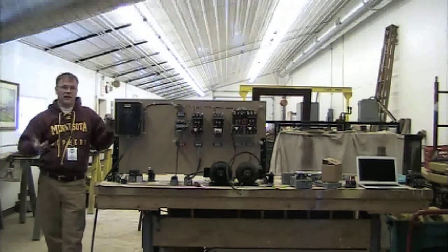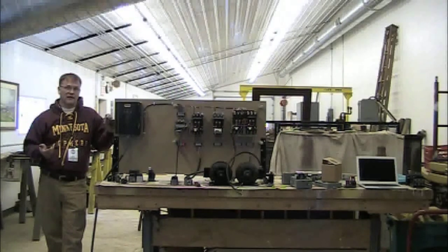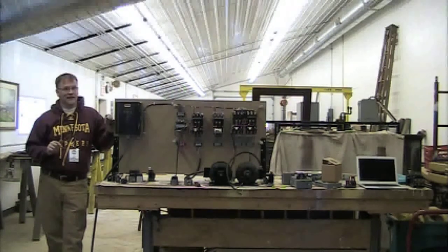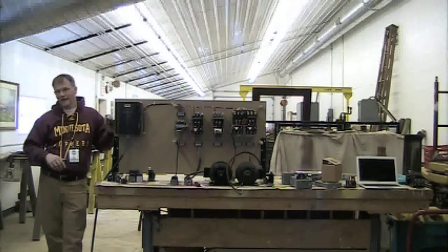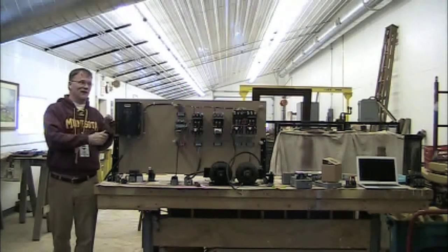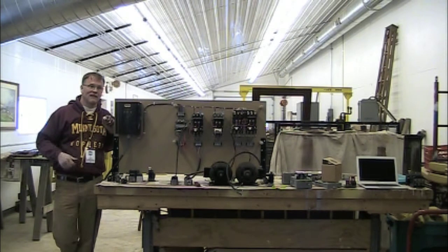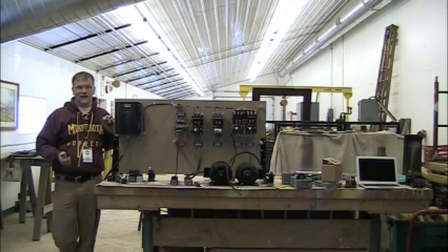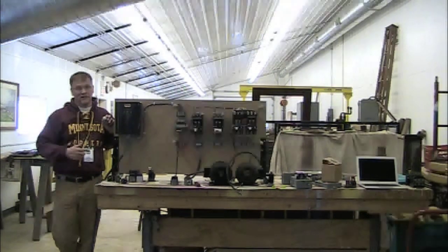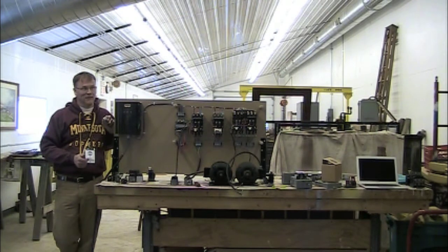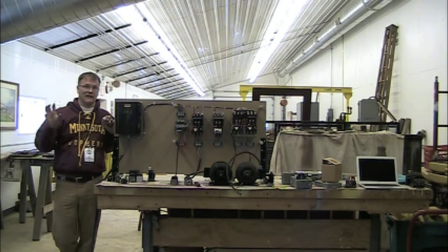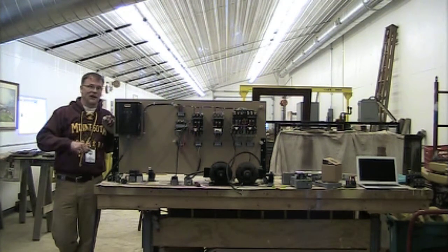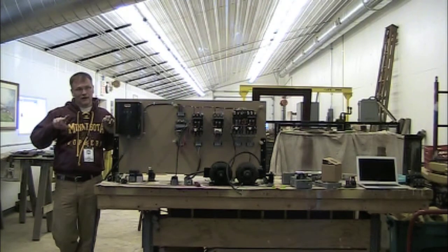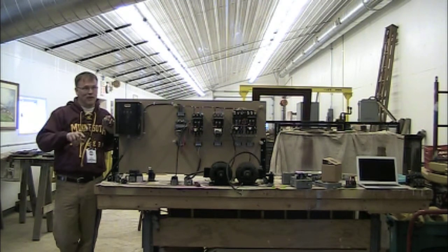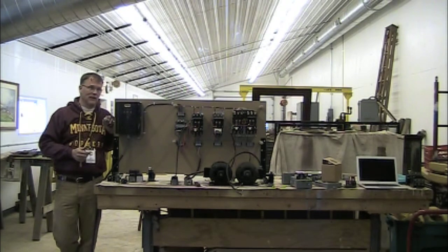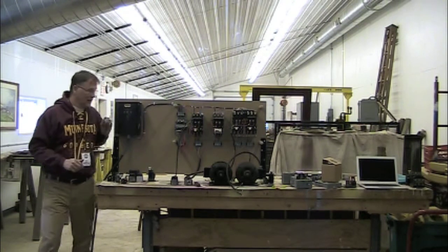Say you want to run a 3-phase air compressor off of a phase converter. Your phase converter is set up so that you start it and you have your air compressor connected to it, and the only thing you have is a switch like this to turn it on and off. You may have forgotten to turn it off. That thing's going to be in line with your phase converter, depending on the design, and it's either going to auto start, or the phase converter is going to try to start your compressor at the same time as well. So that's a way of handling that. If you want to have a mag starter on your compressor, you can have a secondary little control circuit so that you can provide that dropout protection, and you start it when you want to use it.